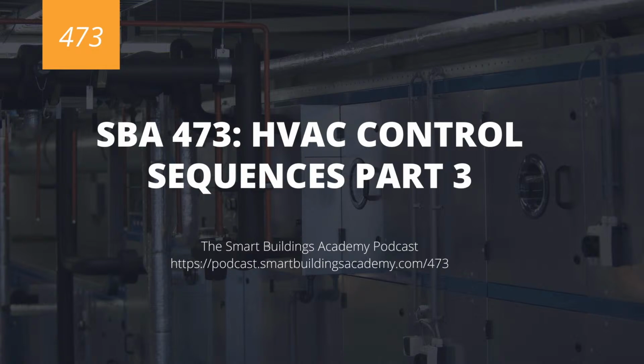So with that being said, let's take a look at these little sequences right here. So single zone VAV, constant volume. All right, so whenever we are working with a constant volume system, and I don't even know why they're calling the sequence VAV, technically it should be CAV, constant air volume unit, but whenever we are looking at a single path air handler, whether it be a variable air volume air handler, whether it be 100% outdoor air unit, whether it be a makeup air unit, we're going to run into some common safeties. The most common of those are going to be fan safeties, and they are going to be smoke control safeties.